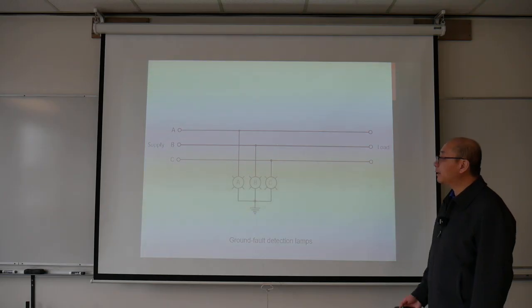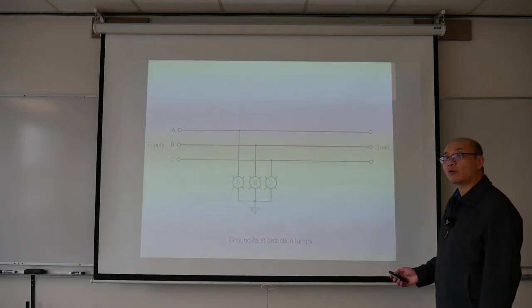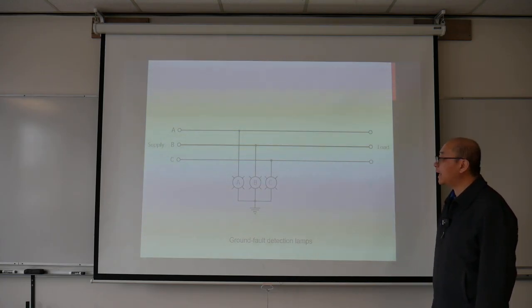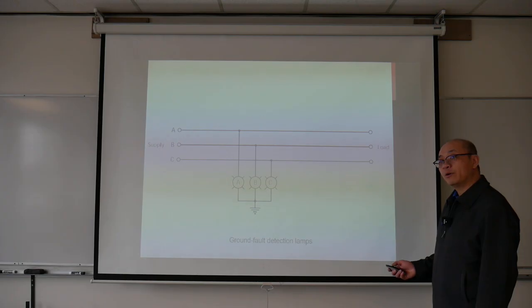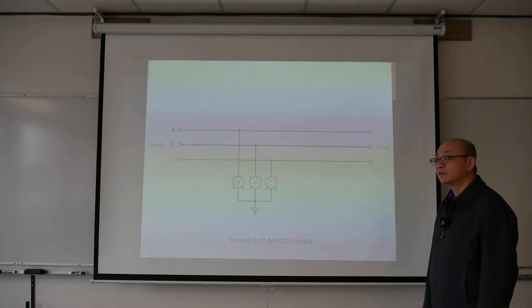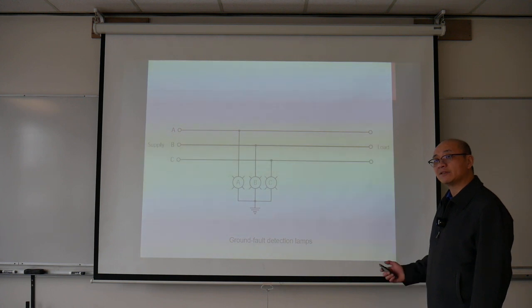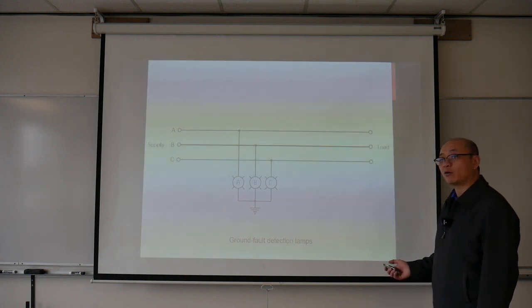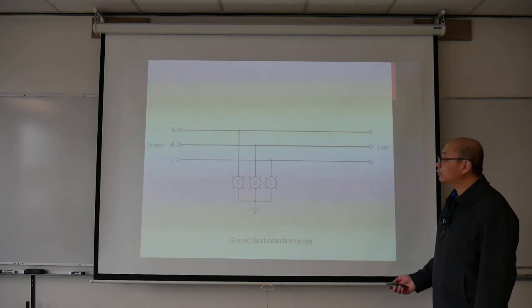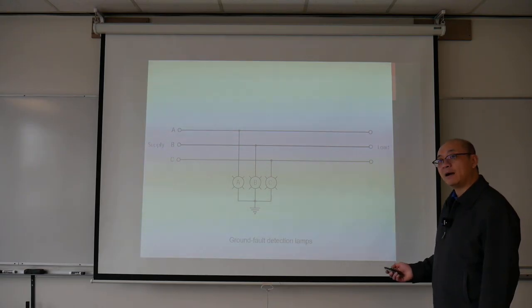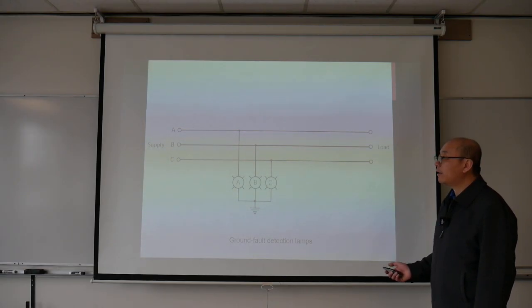In three-phase, we can use three lamps to indicate a ground fault in an ungrounded delta system. But there's a slight problem with this lamp indication, because if one of the lines grounds, then two of the lamps will become brighter, but one of the lamps will become dark. Then we always have to have someone watching those lamps to see if a ground fault happens. So we'd like to put a ground fault detection relay in there, so the relay can send out an alarm signal. Let's say a bell or horn goes off, so we know there's a ground fault happening in the circuit right when it happens.